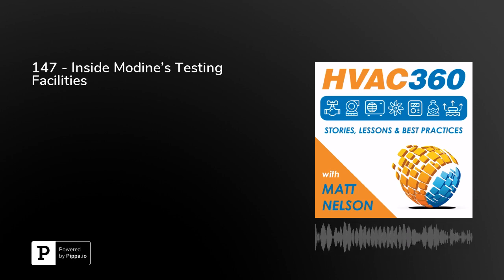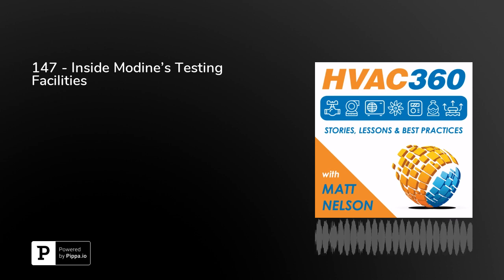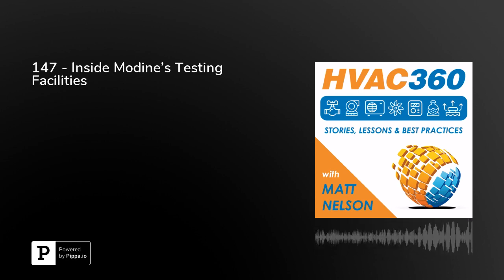The other advantage from our standpoint is the quality that we can do. Ultimately, we can test well beyond the individual test standards. If I look at things like our rooftop units, where we're testing to AHRI 920 and 340/360, and really across all our product lines, we have our standard rating points. Pretty much everyone in the industry tests to those standard rating points, but with our test facilities, it's the ability to test well beyond them.